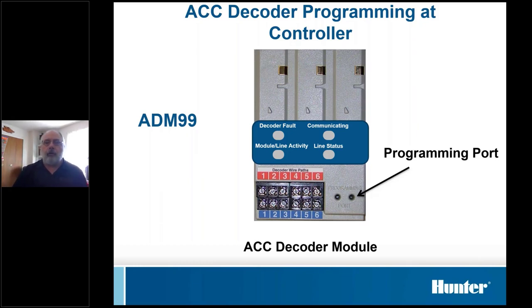And what we did was we programmed the serial number into the controller. The big difference is, if you have a problem with the controller and it has to be replaced, you're going to have to re-enter the serial numbers for all those decoders. Whereas on these systems, if something happens to the controller, you don't have to do anything except replace the controller and program it, because it's just sending out station numbers, and the decoders have been set with the station number. To me, it's a way better way to do it. It makes life a lot simpler down the road with this setup.